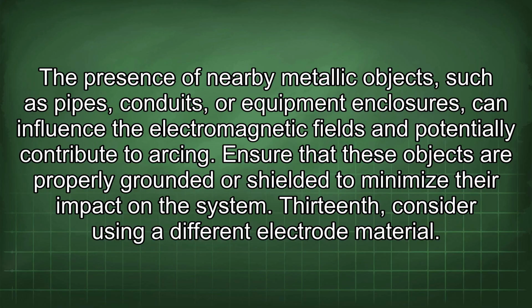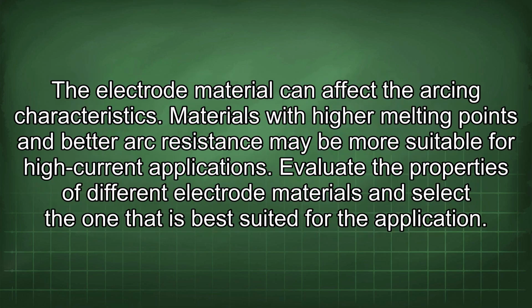13th, consider using a different electrode material. The electrode material can affect the arcing characteristics. Materials with higher melting points and better arc resistance may be more suitable for high current applications. Evaluate the properties of different electrode materials and select the one that is best suited for the application.